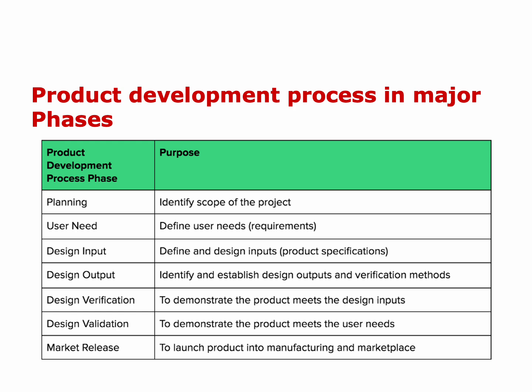So you can validate a software, you can validate a device, you can validate a measuring device, all medical devices, and those validations are going to let us know that each and every functionality that has been designed and then produced is working. And then it shows that the device is validated. We keep that validation document in our files, and we're going to use it as well for the registration of the device. Then we also have the market release. This is to launch the product into manufacturing and the marketplace as well.